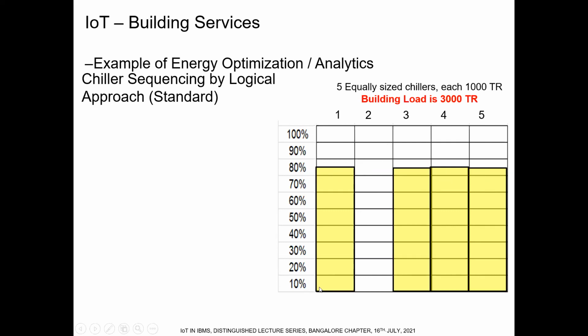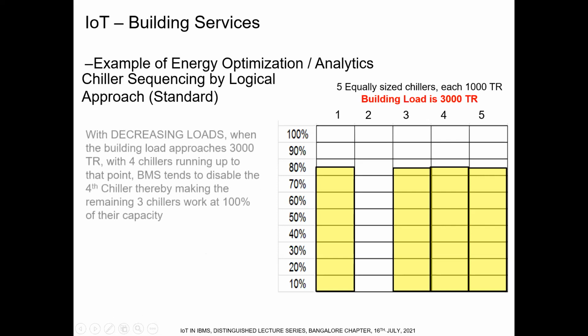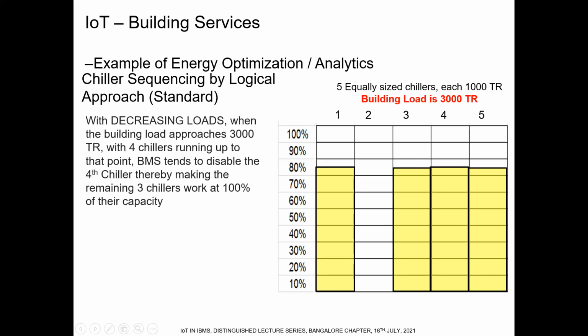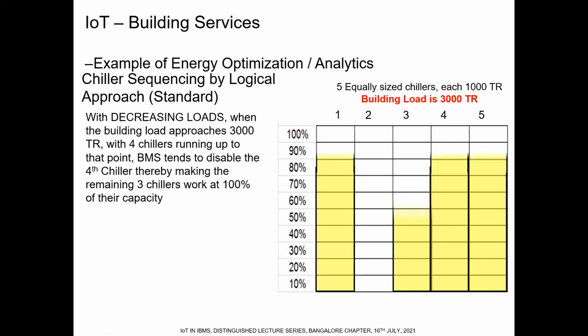What the BMS will do is take out one of the 4 chillers, because the chiller, you know, is a very big energy guzzler. So it takes one chiller out of operation and then pushes the remaining 3 chillers to 1,000 tons. This is the next step of automation. So 3 chillers are now operating at 100% again to produce 3,000 tons, apparently to optimize energy. We are still not looking at the energy consumed by the chiller. This is based on the capacity control methods, the standard method of doing automation.